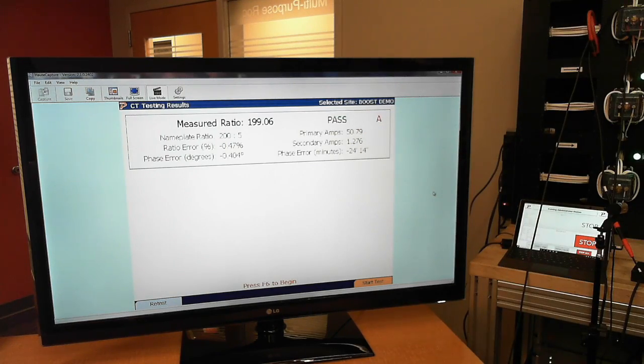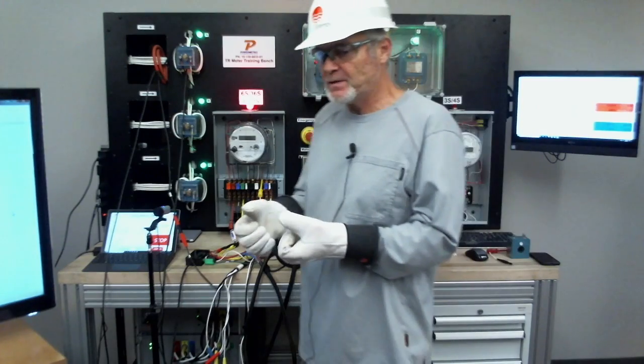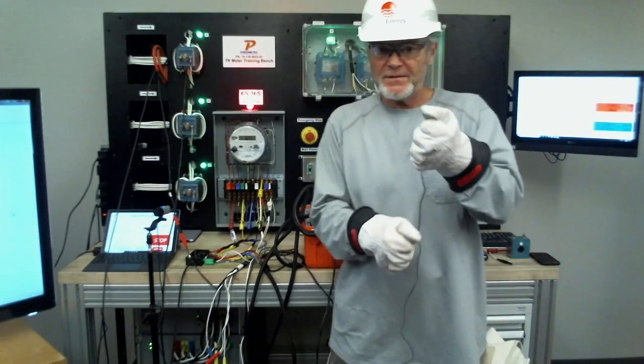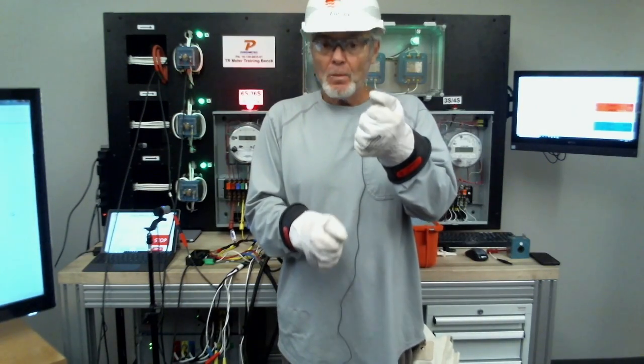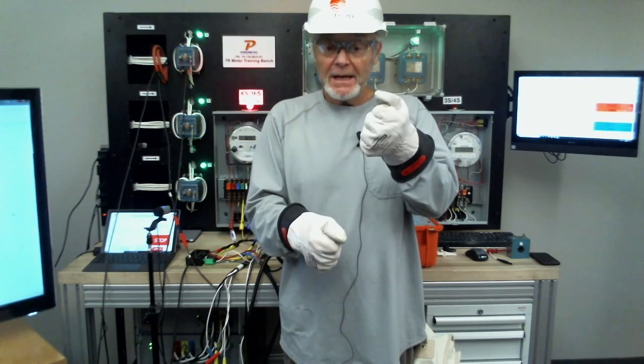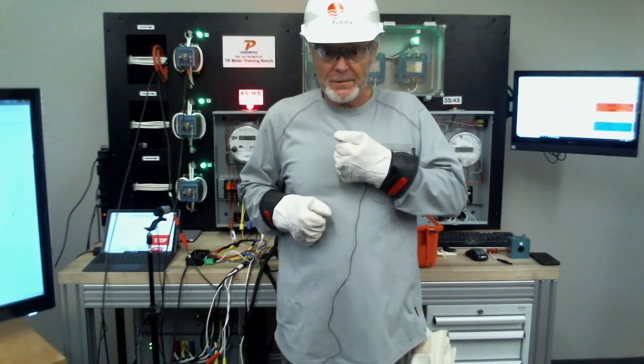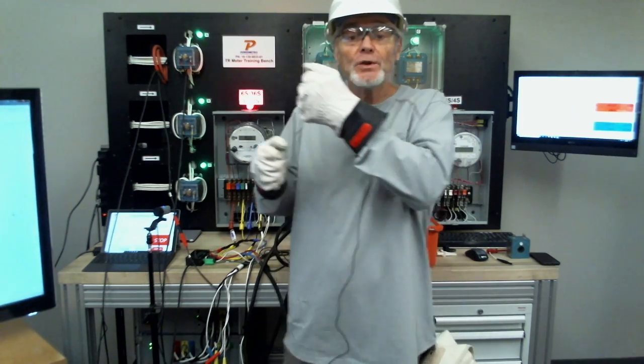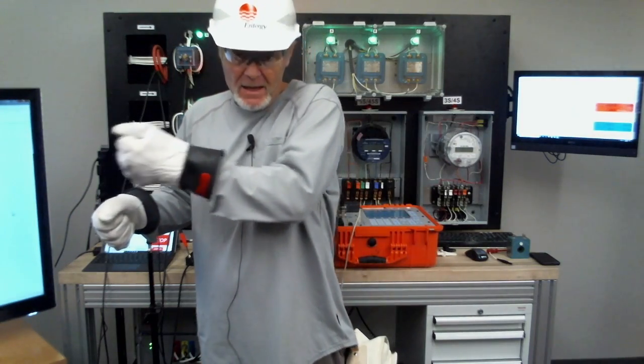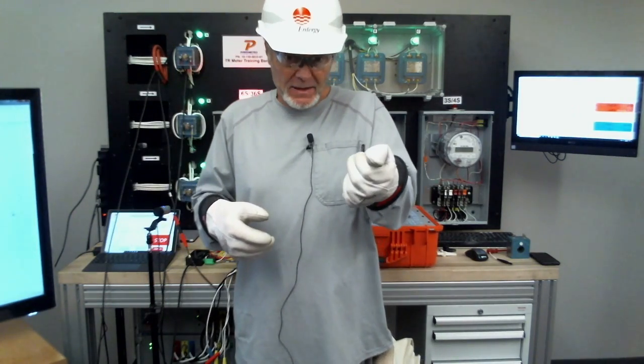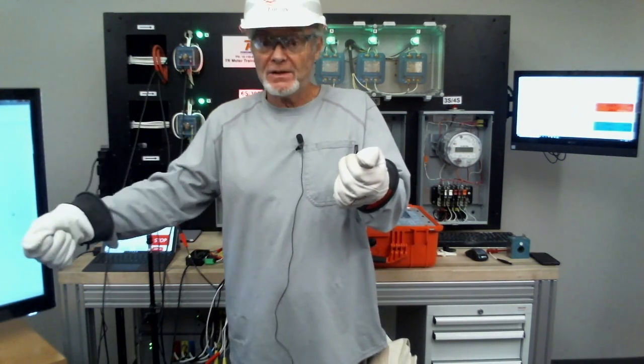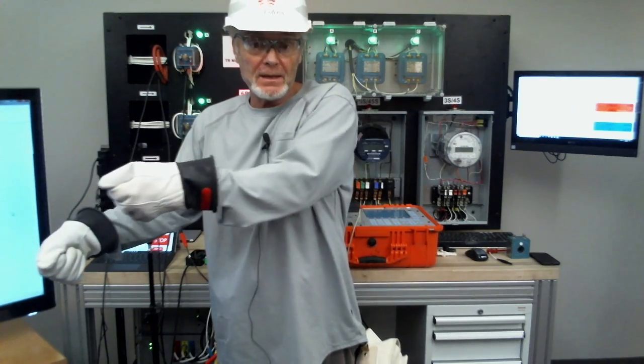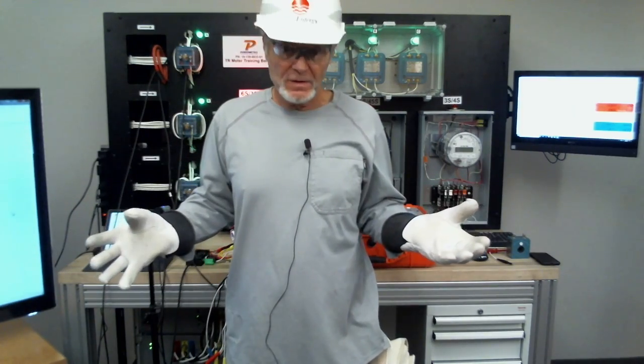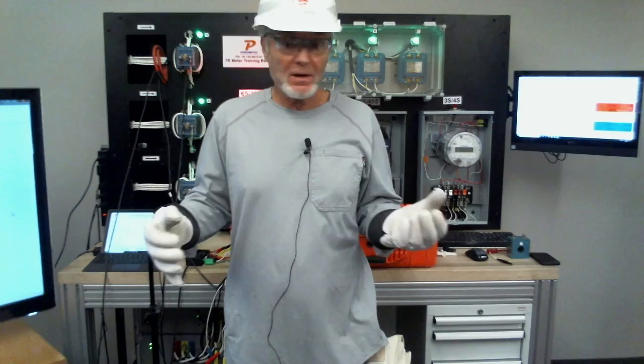Here are some pointers on this when you're doing these. If you're doing a load boost test and you test phase A, when you finish with phase A, disconnect both of your connectors before you move over to phase B. You don't want to still be connected on A and move your connections over before you're disconnected off A. You could smoke some connectors there.